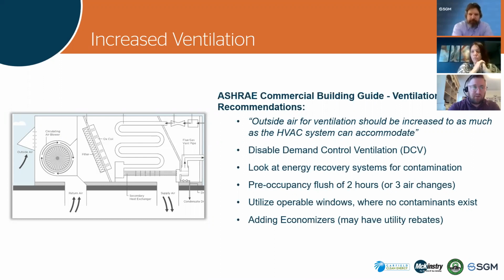You mentioned pre-occupancy flush, and there's a question about what about post-occupancy flush? So depending on which building guide you're reading, post-occupancy is a recommendation. We have implemented that in schools. My personal view is that it's not as necessary as the pre-occupancy flush. If no one is truly in the building, I don't see why you would need to flush it. If you do have people in the building, consider flushing it or keeping it active while those people are there, absolutely. But I think that pre-occupancy flush is really the important one.